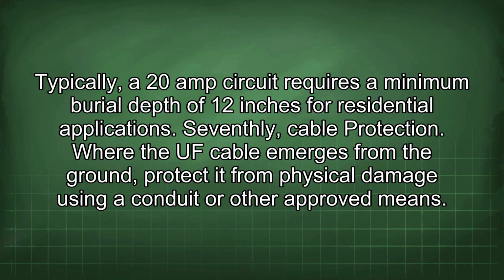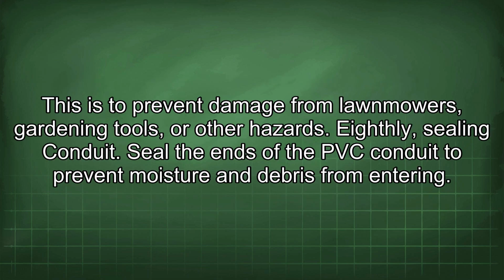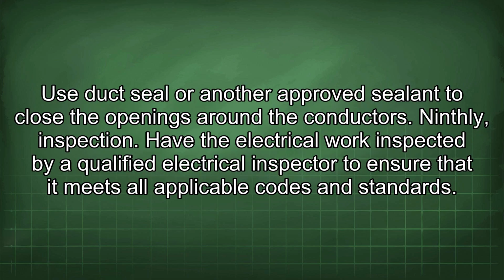Seventhly, cable protection. Where the UF cable emerges from the ground, protect it from physical damage using a conduit or other approved means. This is to prevent damage from lawnmowers, gardening tools, or other hazards. Eighthly, sealing conduit. Seal the ends of the PVC conduit to prevent moisture and debris from entering. Use duct seal or another approved sealant to close the openings around the conductors.